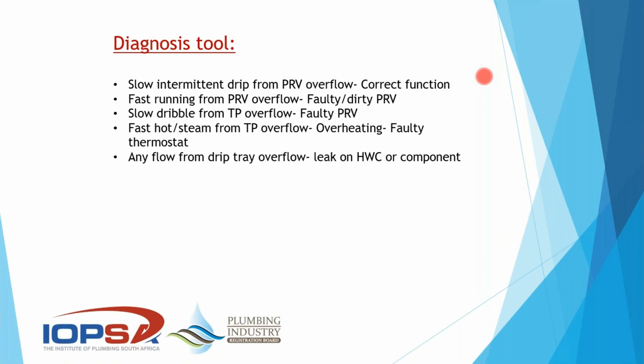All right, so we've got about 30 seconds left. If we can get a quick answer for the following two questions. The first one reads, are 90 degree bends allowed to be used on a tray overflow? As the tray overflow needs a discharge rate of 40 liters per minute. If you can show that using 90 degree bends will still allow for that flow, then yes.